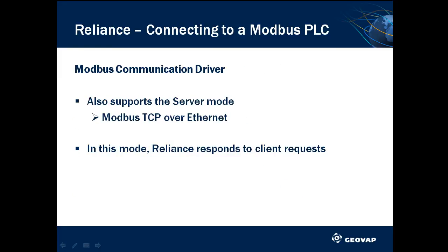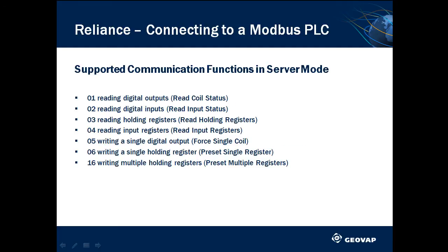In addition to the client mode, the Reliance system allows activating the server mode for a Modbus device. In such a case, the Modbus communication driver does not read data from this device, but it allows, via the Modbus TCP protocol, another client to read and write data from or to this device over Ethernet. Here is a list of all supported communication functions in the server mode.